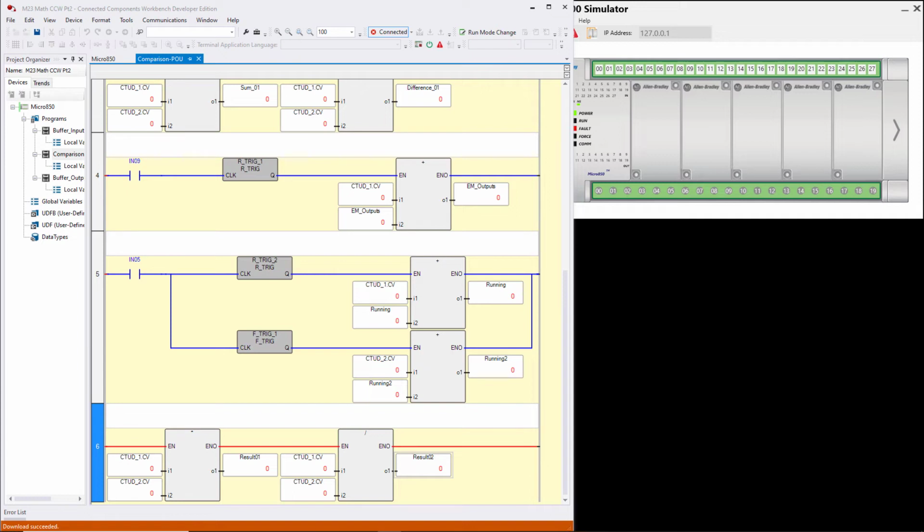Would the results be different if they were each in their own rung? No. They're somewhat autonomous. In other words, one's not dependent on the other, especially since rung 6 is unconditionally true. You could stack up a dozen of these math type instructions in series, and they're all going to execute fine regardless of the results of any one individual instruction.